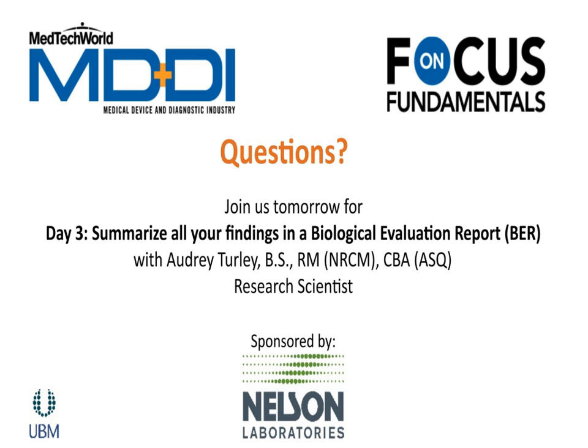But E&L can also be used to target something. For instance, I used this nitinol example, looking at the nickel being released. That could be a really quick turnaround study. We could get results back within a week, and we know we're only addressing nickel, so we could have quoted out the toxicological risk assessment in advance just for nickel. In the process, we could be evaluating nickel based on the patient contact of the device and have things going in tandem.